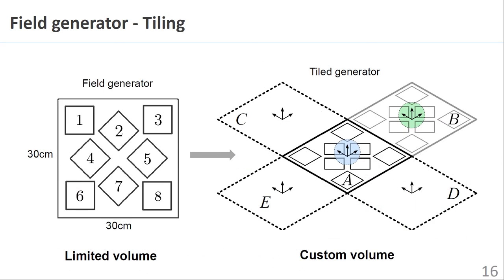Tiling of multiple field generators is then possible since the relative origins of additional field generators can easily be determined if they are placed together and share a common edge as shown. This provides a simple means of expanding the total spatial tracking volume in which a magnetic sensor can be tracked.